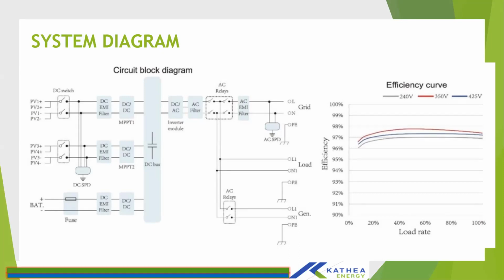However, when you're installing PV, it's recommended to install a protection box, which is basically fuses and surge protectors. Although the system has a built-in DC SPD surge protector, which is also a type 2, it's recommended that you also install an external protection box. Then it goes to the filtering circuits up until the DC to AC conversion. And on the output side, on the AC side, the system is also equipped with a built-in AC SPD for your protection. So this is how the internal structure of the inverter looks.